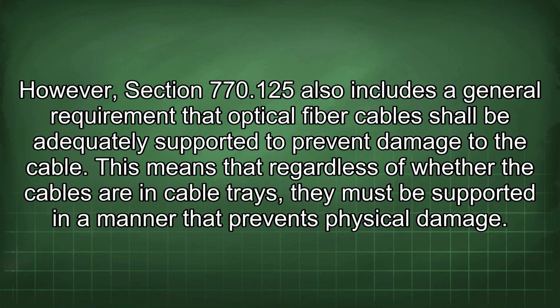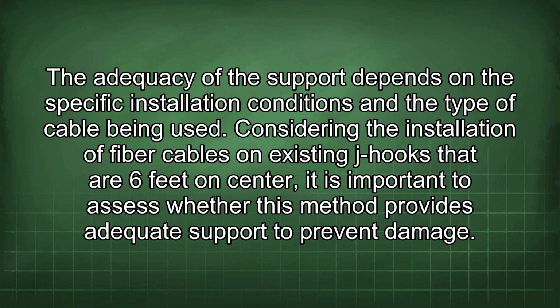However, Section 770.125 also includes a general requirement that optical fiber cables shall be adequately supported to prevent damage to the cable. This means that regardless of whether the cables are in cable trays, they must be supported in a manner that prevents physical damage. The adequacy of the support depends on the specific installation conditions and the type of cable being used. Considering the installation of fiber cables on existing J-hooks that are 6 feet on center, it is important to assess whether this method provides adequate support to prevent damage.